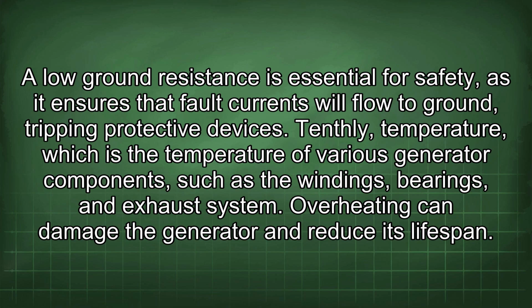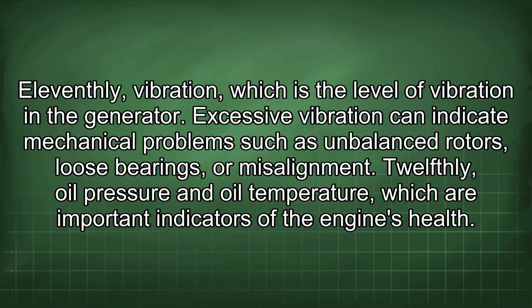Tenthly, temperature, which is the temperature of various generator components such as the windings, bearings, and exhaust system. Overheating can damage the generator and reduce its lifespan. 11thly, vibration, which is the level of vibration in the generator. Excessive vibration can indicate mechanical problems such as unbalanced rotors, loose bearings, or misalignment.